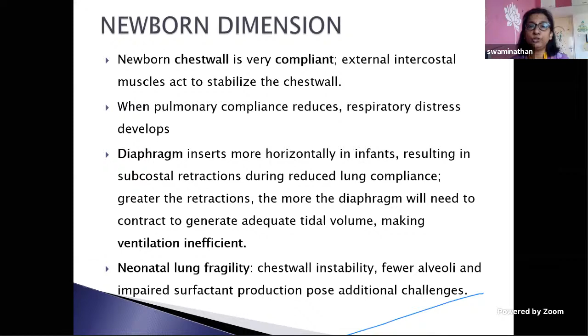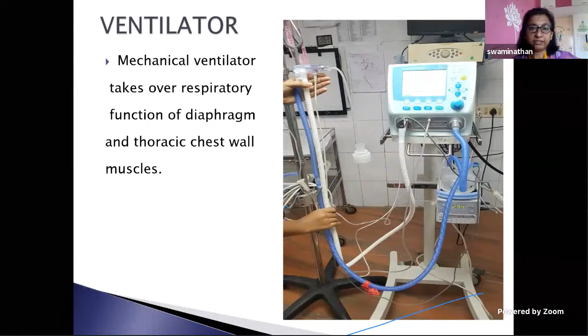As we all know, this is a ventilator which we set. We put the tubings. The tubings are connected from the ventilator to the humidifier, and then the inspiratory limb. Then it goes to the baby through the endotracheal tube. I put a test lung here. Once the lung gets inflated, the air will come out through the expiratory limb. And there is a flow sensor. There is a thermal sensor to monitor the temperature from the humidifier. The humidifier should be connected to the inspiratory limb. That much you have to do. Many hospitals will have respiratory therapists and manifold room people who will come and set the ventilator. But in our hospital, our nurses do the ventilator setting up.